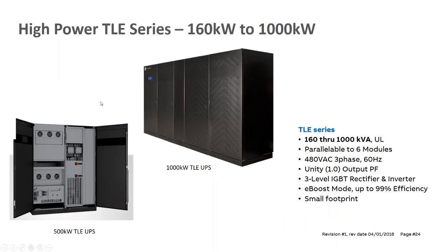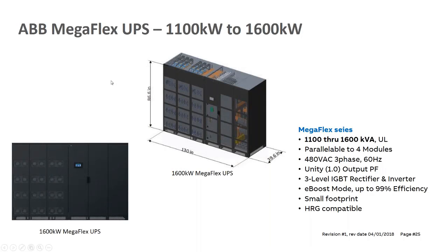The bigger brother, the high-power TLE, and that's that 500 which we saw before. It's available from 160 kVA up to 1 megawatt. But very, very similar IGBT-based modules, rectifier and inverter. So similar features, efficiency just shy of 97% in online mode, and they can do economy mode. So the high power TLE from 160 kVA to 1 megawatt.